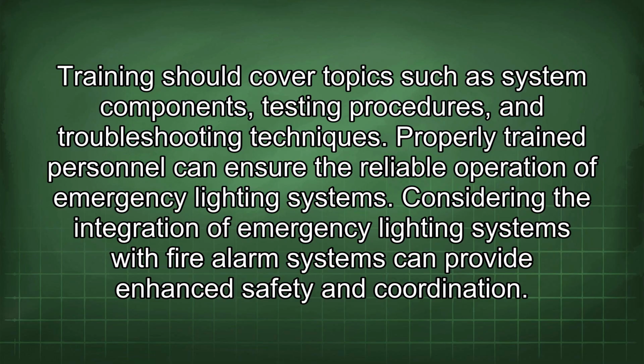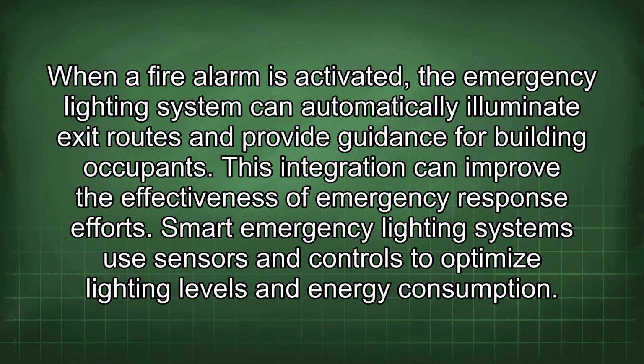Considering the integration of emergency lighting systems with fire alarm systems can provide enhanced safety and coordination. When a fire alarm is activated, the emergency lighting system can automatically illuminate exit routes and provide guidance for building occupants. This integration can improve the effectiveness of emergency response efforts.